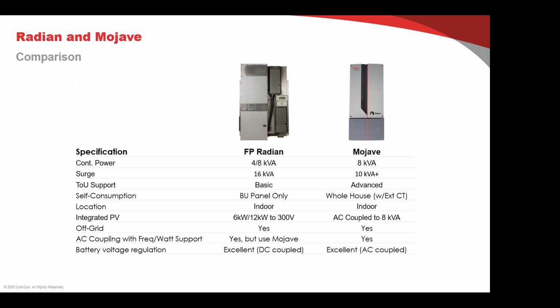Okay, in terms of integrated PV, right now it's just AC coupled up to 8 kVA. Off-grid, that's kind of what OutBack is known for. Normally, I would say never do AC coupling on an off-grid situation because you're going to be cycling the batteries every day with poorly regulated DC charging. And I always tell people don't do it, especially with lithium batteries. AC coupling is not a good idea.